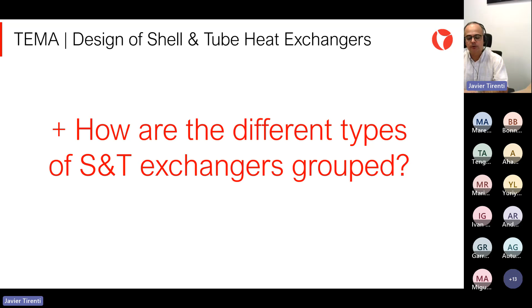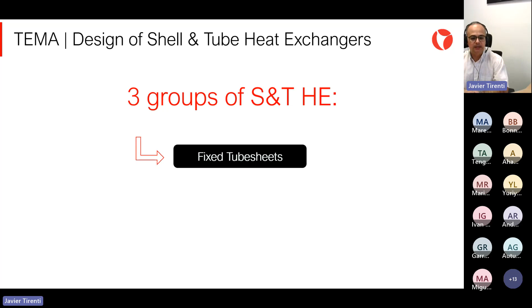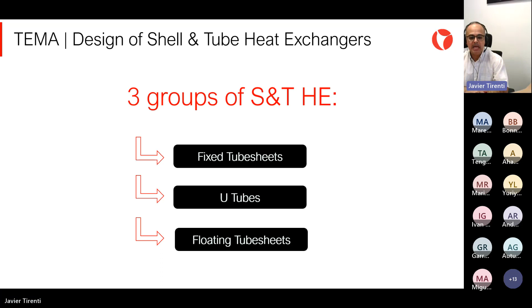Okay, let's move on to the groups. How are the different types of shell and tube heat exchangers grouped? There are mainly three groups of shell and tube heat exchangers. One of them is the fixed tube sheets group. We have the U-tubes group. And then we have the floating tube sheets group. Let's go into a little more detail with these groups. The shell and tube heat exchangers with fixed tube sheets and straight tubes adopt configurations as we can see on the screen: BEM, AEM, NEN, as per the TEMA designation.